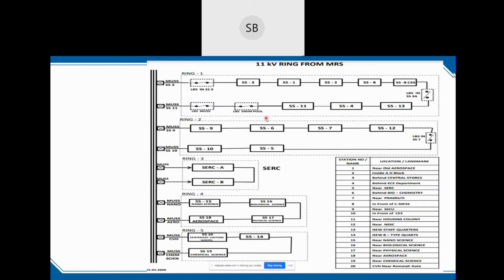We have tried to pool each ring. Say ring 1 consists of a certain number of substations, similarly ring 2, ring 3, which are important where power interruption needs to be minimal. In such cases, if a transformer on the way gets affected or disturbed, immediately, with the help of the load break switch, we connect it to the nearby transformer, and power is restored within a very short period. These ring mains have been done for the entire campus, and depending on the load of each department, we have made 5 rings.